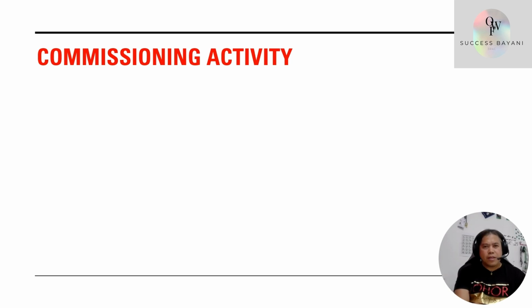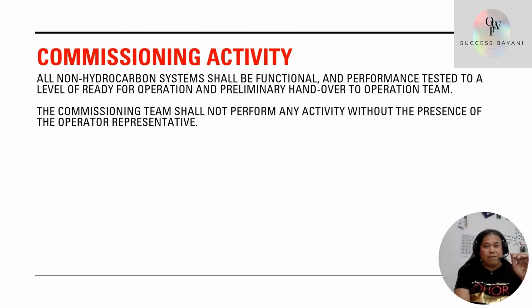Now, commissioning activity - we will put it all in one place. All non-hydrocarbon systems shall be functionally and performance tested and made ready for operations. The commissioning team shall not perform any activity without the presence of the operator representative. What does that mean? During commissioning, guys, based on my experience, commissioning focuses on how to commission the system and equipment, since we have system and subsystem integration across all disciplines - mechanical, piping, E&I, telecommunications, HVAC, etc.